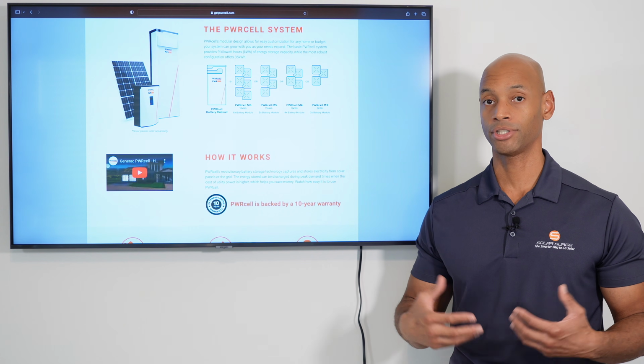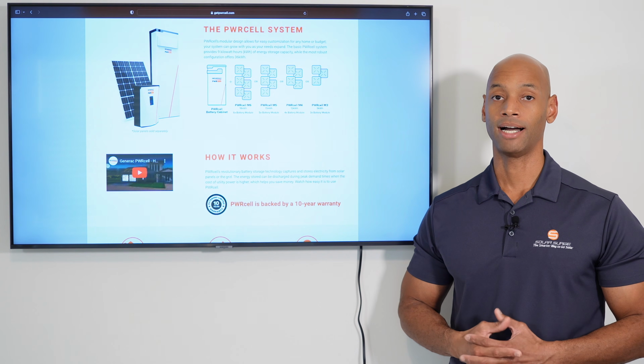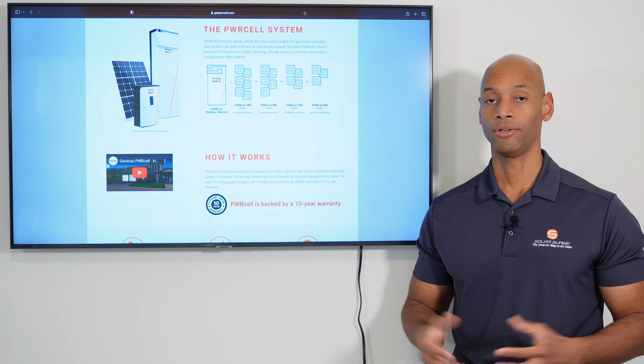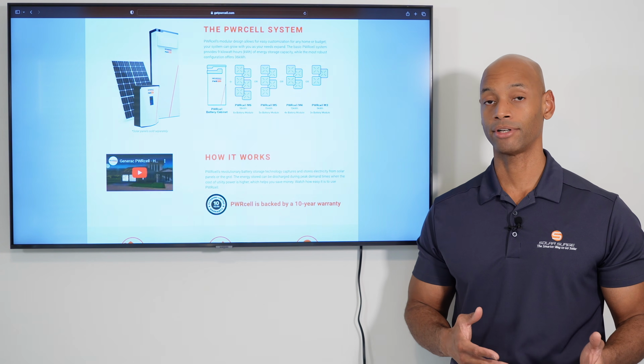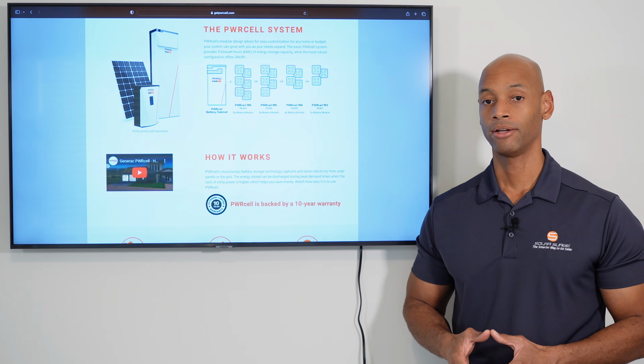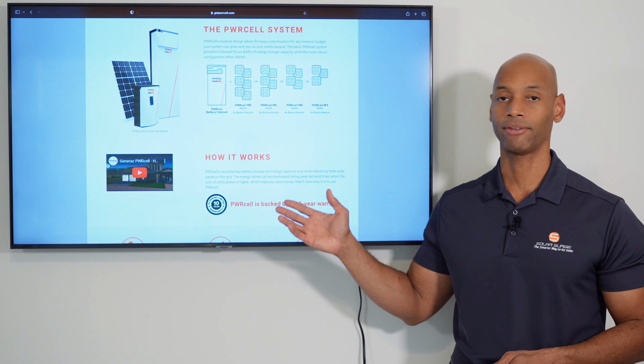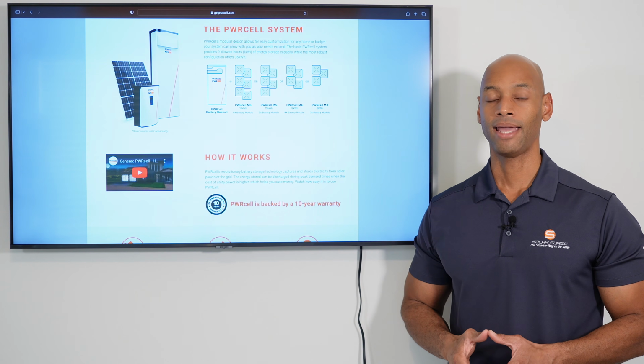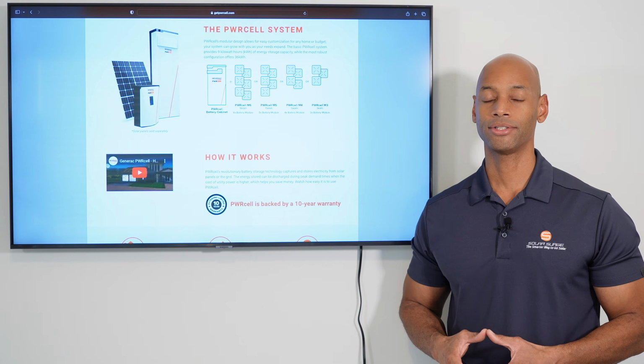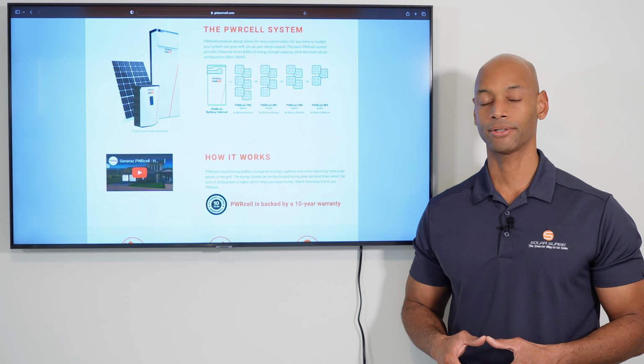Also, in terms of continuous load power, compare it to the Franklin—you can do 10,000 watts off the batteries only with a 2 battery system. With the Generac PWRCell system, the most you could ever get out of it was 9,000 watts. Part of the reason is that's one of the limitations of the DC coupled architecture.